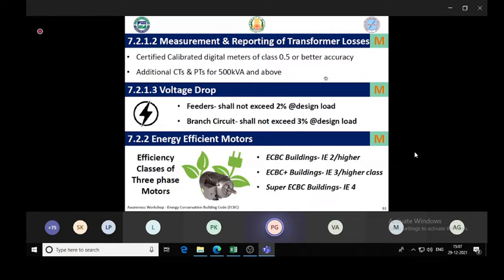And after installing the transformers, the transformer loss should be measured using class 0.5 calibrated energy meters, as well as for continuous loss monitoring. So for example, you may have to monitor your transformer loss every 6 months or 1 year. For that purpose, additional CTs and PTs should be provided on the transformer primary and secondary side.